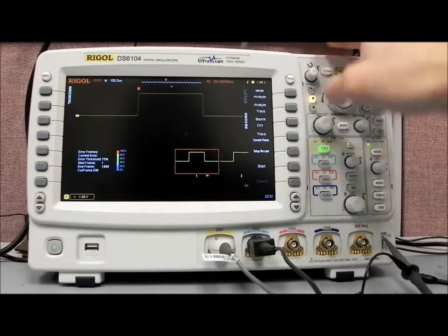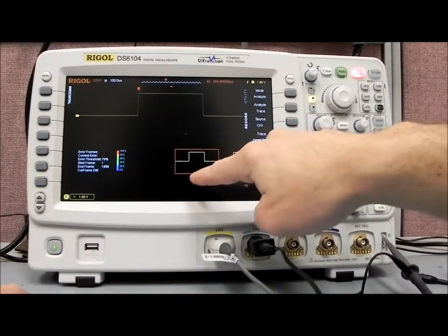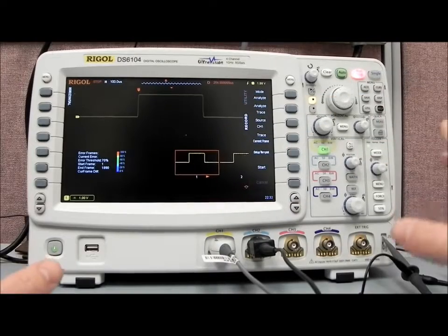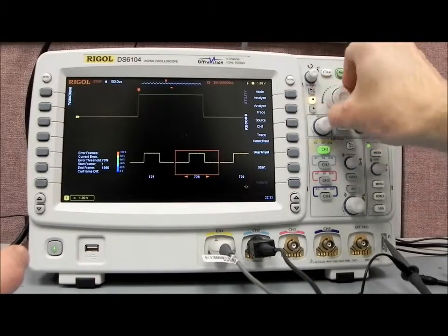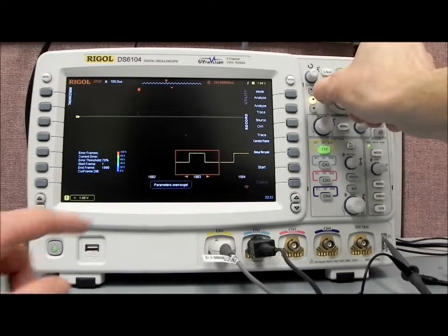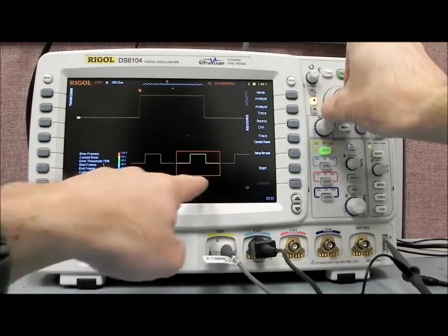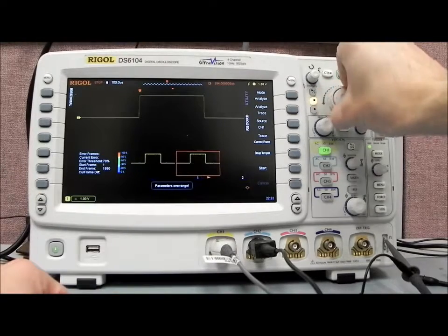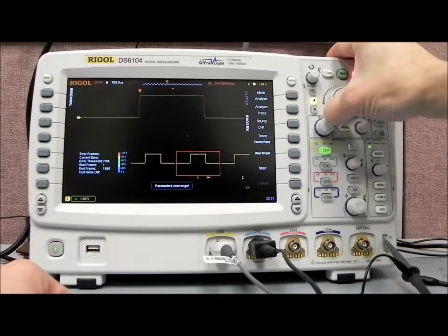In Analysis, you'll see we now have a split screen. On the top screen, we have a picture of the first frame, or the first waveform that we've collected in memory. We can select any of those using either the outer UltraVision knob, which gives us a fast-forward effect. You can see that we're zipping along now, we're at 1,890 frames. Or we can go one at a time using the inner knob, where we go 5, 6, 7, 8, and back again.